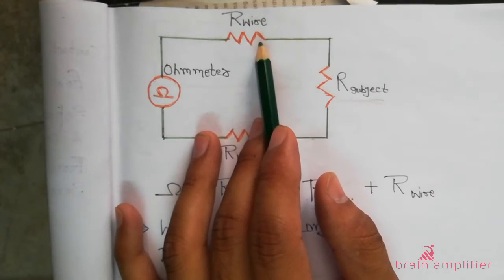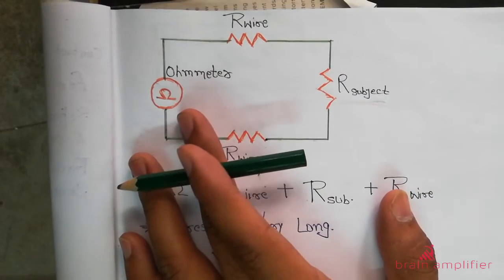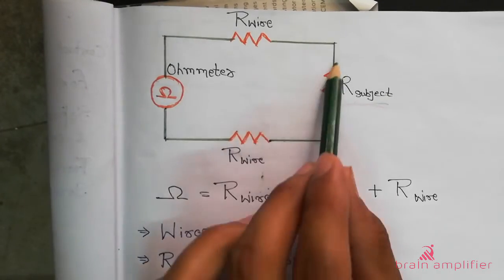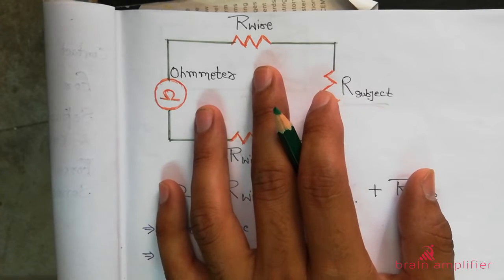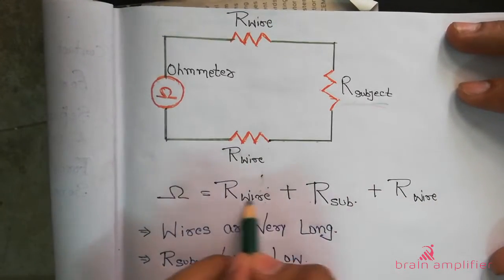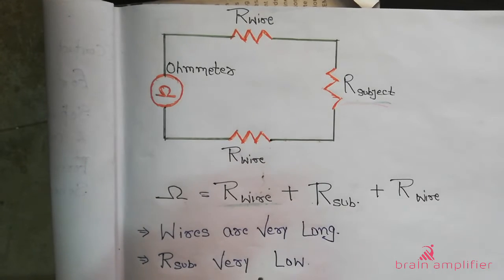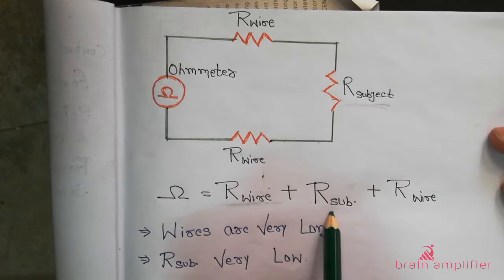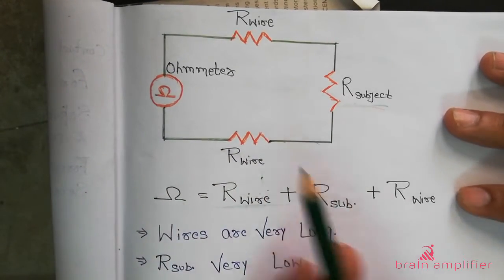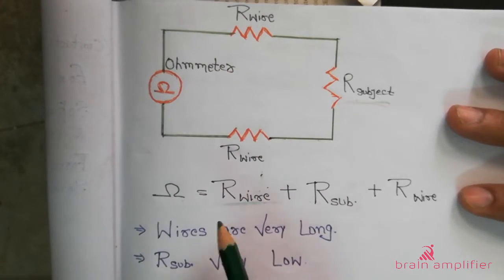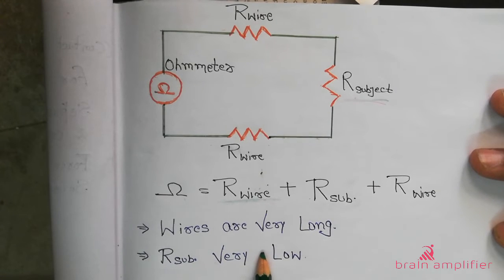Now suppose I have to take a measurement from some distance — say 40 or 50 meters. In that case, R_wire becomes significant. Since R equals rho times L divided by A, if the length is high, the resistance will be higher. So R_wire becomes an impurity — an error — in the measurement of R_subject. If R_subject is very high and R_wire is very less, this error can be neglected. But if the wire length is very high, R_wire becomes significant and the measurement becomes erroneous.